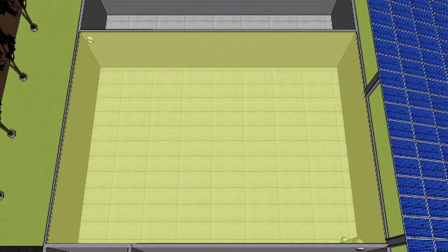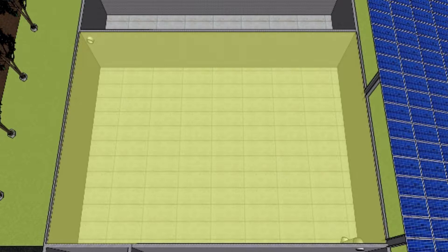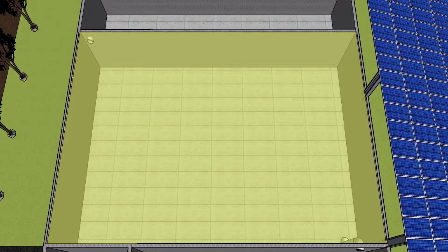In the anaerobic tank, heavy shock loads will be handled by the process. Organic material will be digested and methane and carbon dioxide gases released. It liquefies slurry and semi-solids, and denitrifies nitrogen for further homogenization of the septage. Return flow is provided from the aerobic tank in terms of biological water, which has a very high density of microbes, for further biological treatment.